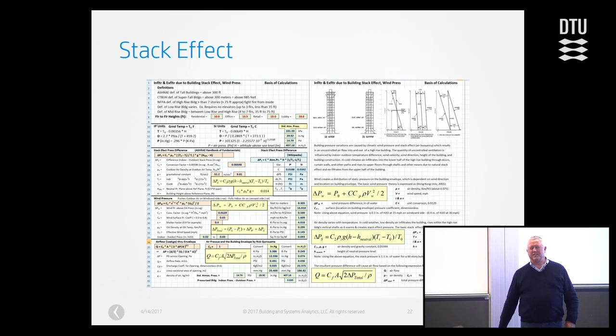The important thing about the stack effect is where the neutral pressure is going to be. That's where the outside pressure and the inside pressure intersect. It isn't, as most people say, 50% of the building, because it varies.